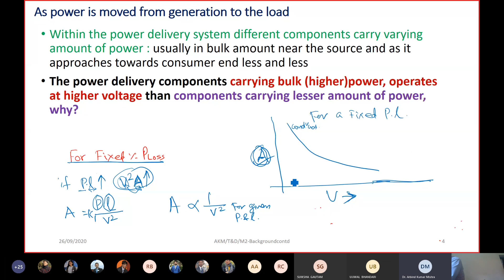So as conductor cost changes, there is another cost also associated with the transmission line. The two basic costs: one is conductor cost, and second is insulator cost. Insulator cost is roughly proportional to the voltage level. For example, if you have an 11 kV system and you go for a 33 kV system, you may require 3 times more insulator, or something like this.